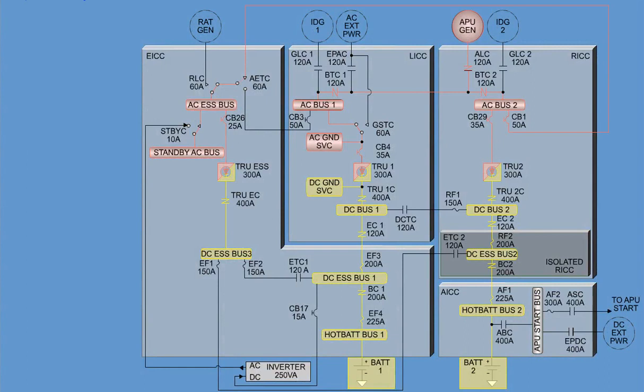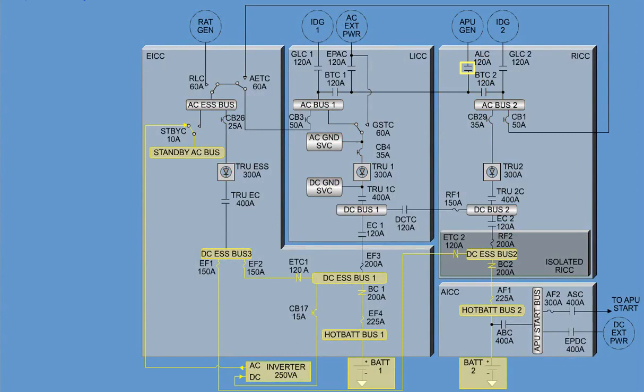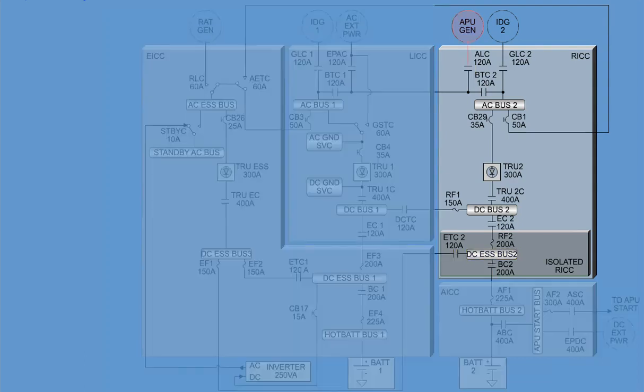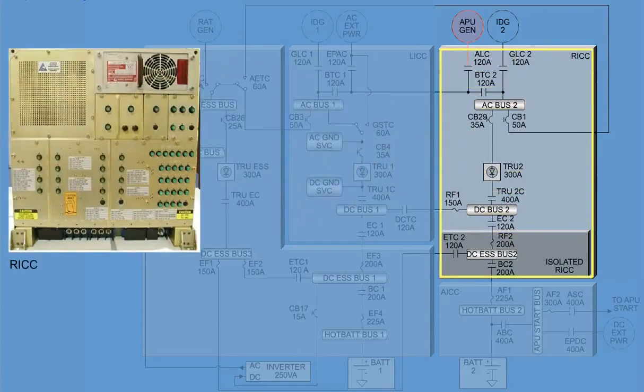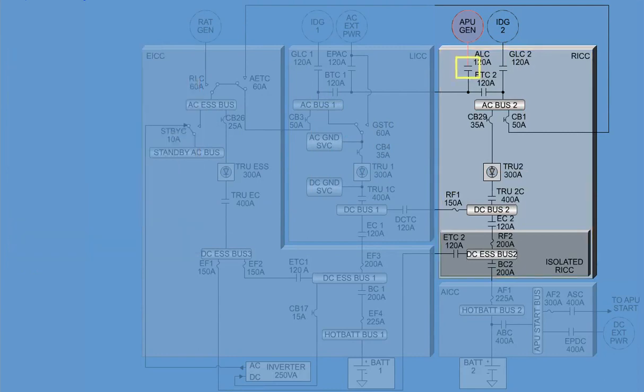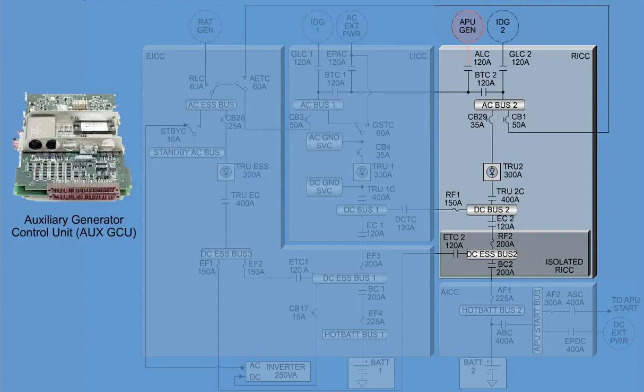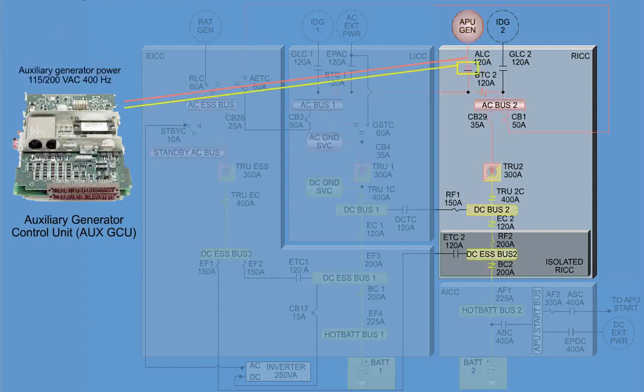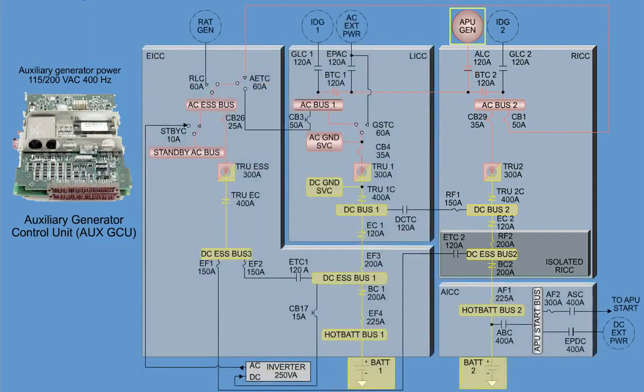If a fault occurs, the GCU will command the auxiliary line contactor to open and stop AC power supply to the aircraft AC power system. The auxiliary generator line contactor is a line replaceable module located in the Right Integrated Control Center. The ALC is normally held open by the auxiliary generator control unit. When the auxiliary GCU has determined that the auxiliary generator power is at 115 to 200 volts AC, 400 Hz, it sends a signal to close the auxiliary generator line contactor, which allows the auxiliary generator to supply AC power to AC bus 1 and AC bus 2.